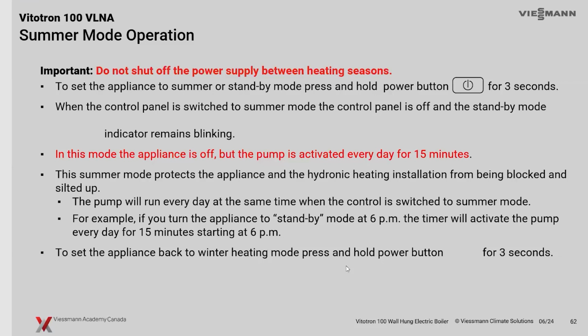Essentially, it happens at the exact time that you put it into standby. So if I was to do that right now, it's like 10:51 right now in Langley, and I put our boiler into standby at 10:51, then every day while I'm in standby, it's going to put this pump into 15 minutes of pump exercise. So we're going to exercise that pump so we don't have it seize up when we want it during the heating season.